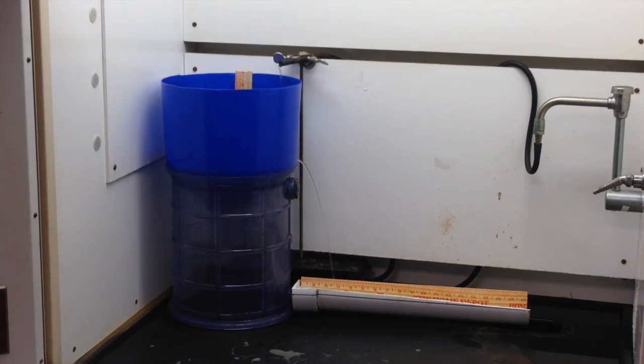Okay, the flow rate into the top of the pan has now been adjusted to maintain an equilibrium level of 1 inch in the distribution pan, in the blue pan. And you can see that the flow rate going in the top is indeed quite a bit lower. And of course, the flow rate coming out the bottom is also quite a bit lower. It's hitting the ruler at about the 3-inch point, where at a pan depth of 5 inches, it was hitting the ruler at almost 12 inches.